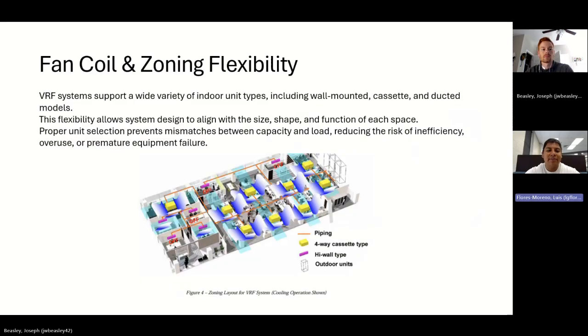Fan coil and zoning flexibility. VRF systems support a wide variety of indoor unit types, including wall-mounted, cassette, and ducted models. This flexibility allows system design to align with the size, shape, and function of each space. Proper unit selection prevents mismatch between capacity and load, reducing the risk of inefficiency, overuse, and premature equipment failure. Here we have a zoning layout for a VRF system.